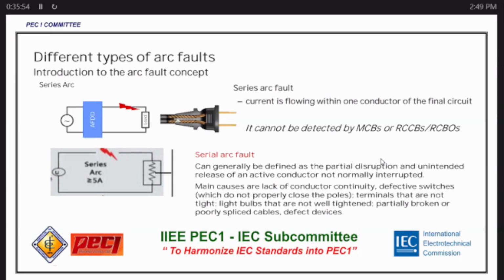No? So series arc fault can generally be defined as a partial disruption and unintended release on an active conductor not normally interrupted. So main cause, lack of conductor continuity, defective switches which do not properly close the poles, terminals are not tight, no? Just like in the light bulbs, no? So even ang light bulbs pala natin, if it's not tightened properly, ito pala tinatawag na series arc fault, no? And partially broken or poorly spliced cable or defective devices.